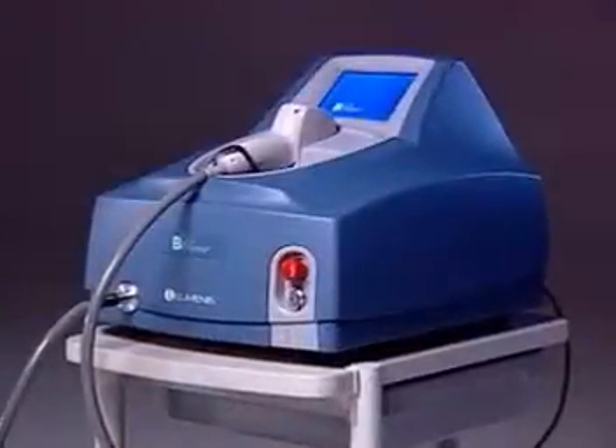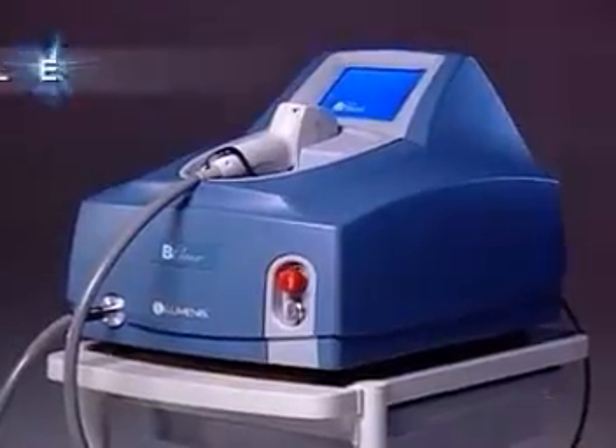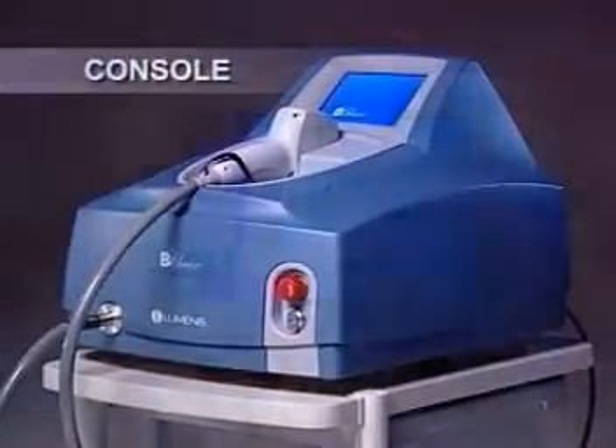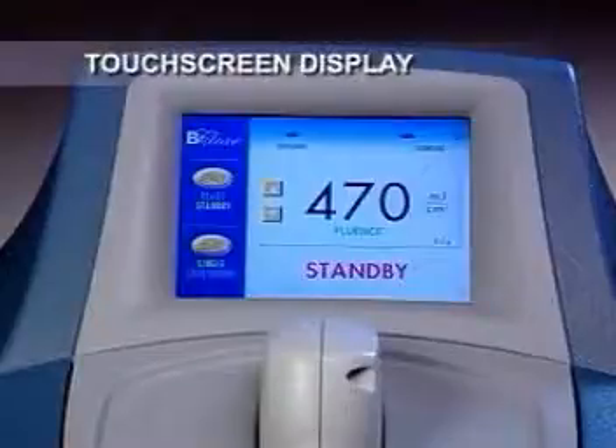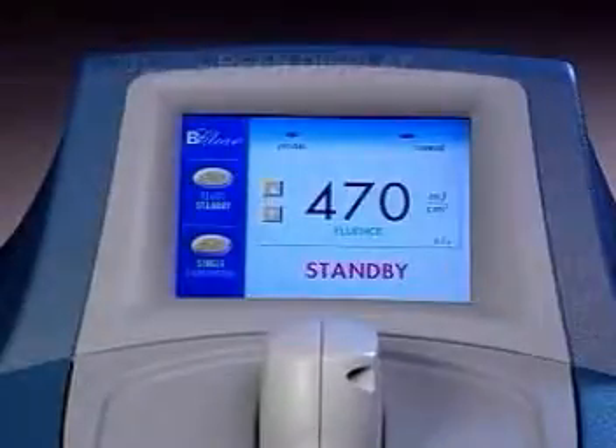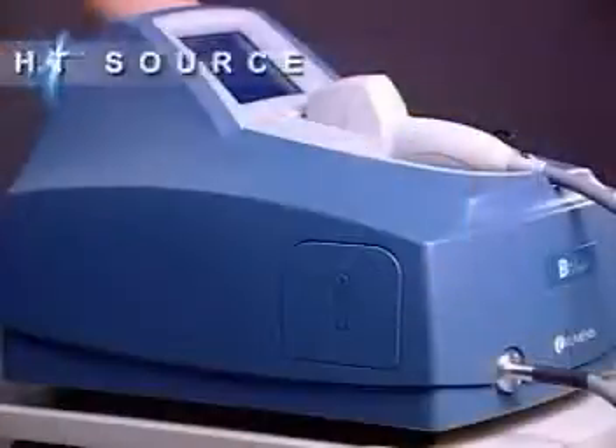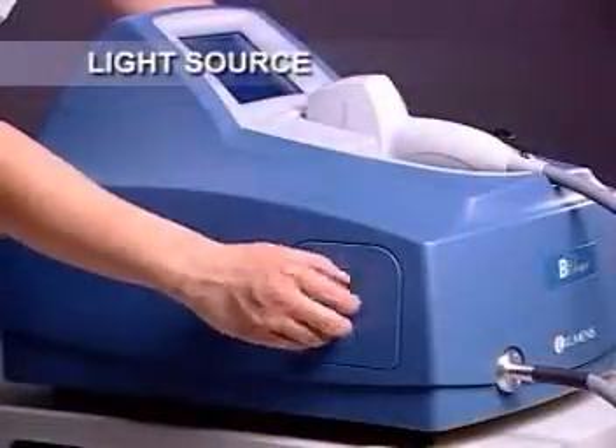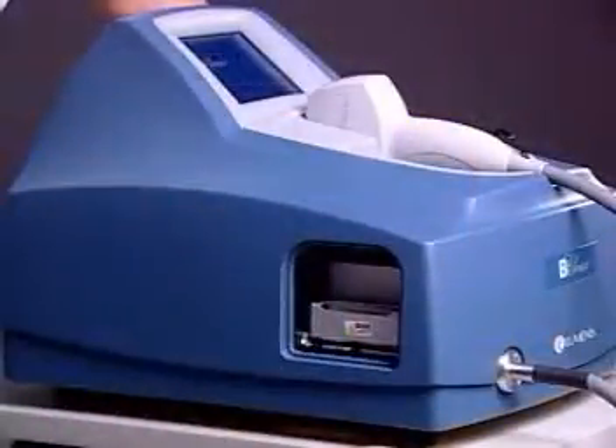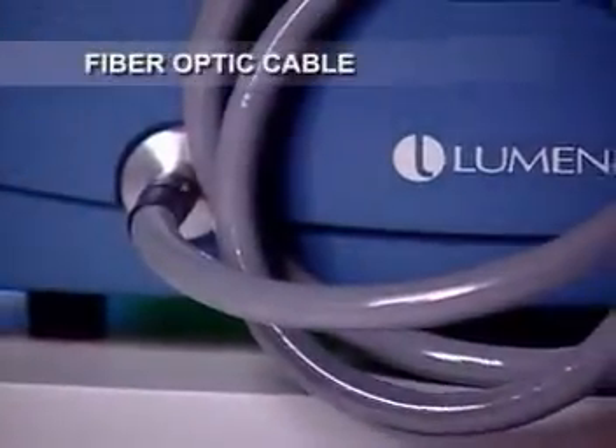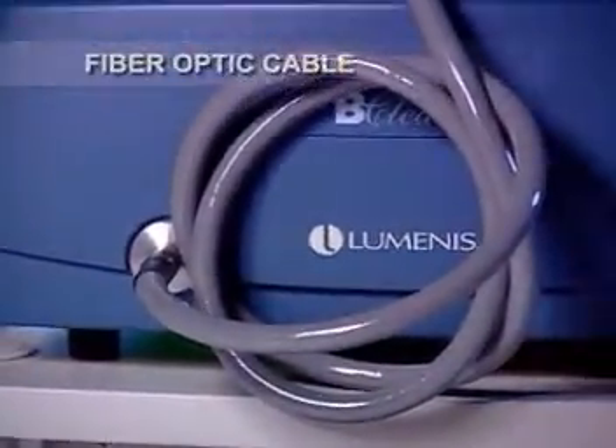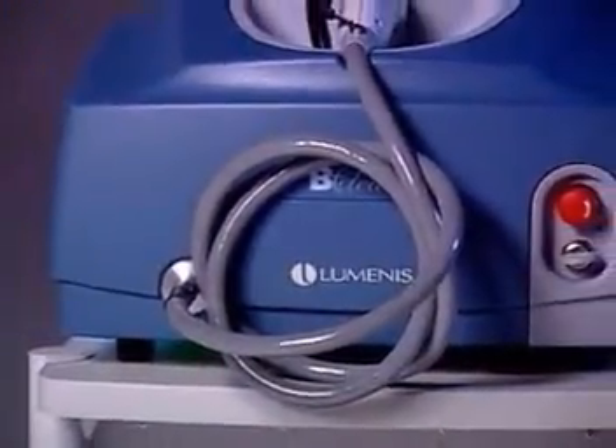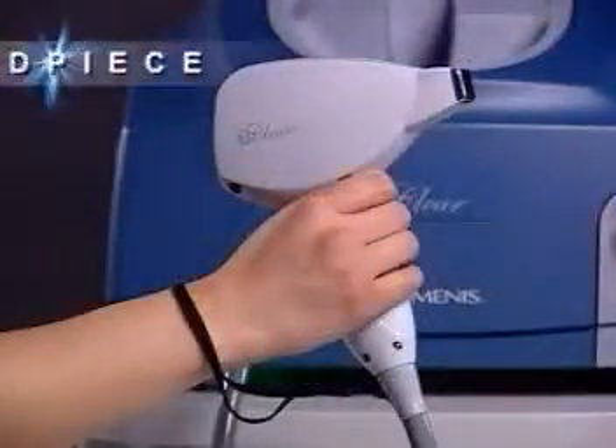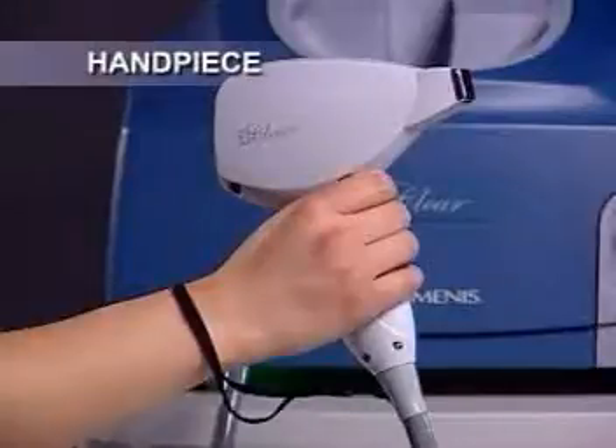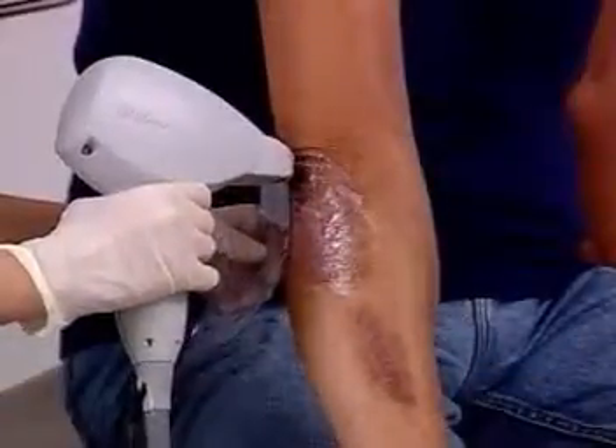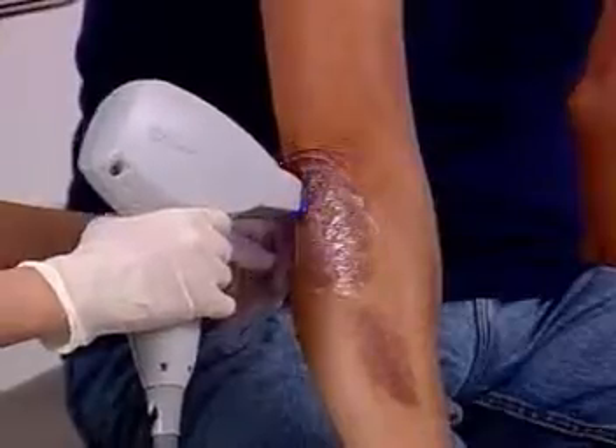Your BClear system includes the following components: console, touchscreen display. The touchscreen display is the way you'll interface with the system. Light source. Easily removable door provides access for replacing the light source. Fiber optic cable. Light is transmitted from the console to the handpiece via the fiber optic cable. Handpiece. You'll use the handpiece to deliver UVB treatment. The handpiece contains delicate optical components which may be damaged if dropped.